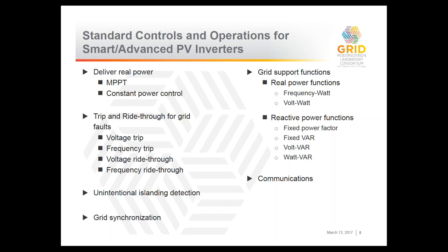So a basic function for a PV inverter is to deliver real power. Typically, it follows a maximum peak power, so it has maximum peak power tracking. But you can also operate that inverter outside that maximum peak power tracking in a constant power control. Some of those inverters, the older ones, have voltage and frequency trip. That means if there is a grid voltage or frequency imbalance, the inverter will trip. With more and more penetration from renewable energy and distributed PV, we are looking into some additional functions to support the grid rather than just tripping off. So some of those are voltage and frequency ride-through that are currently being implemented in those new inverters.